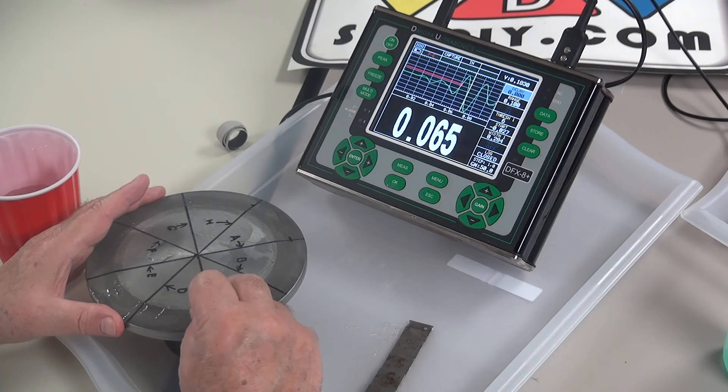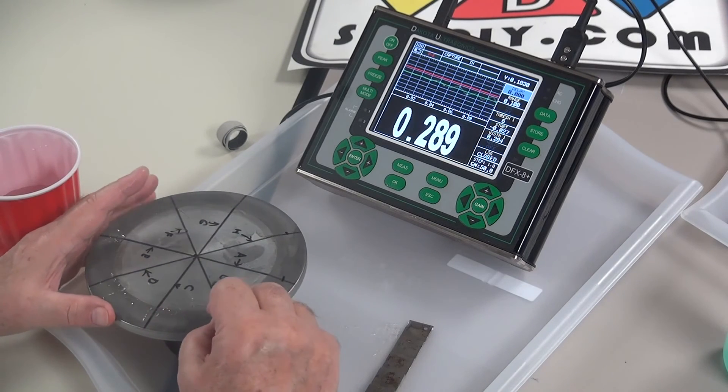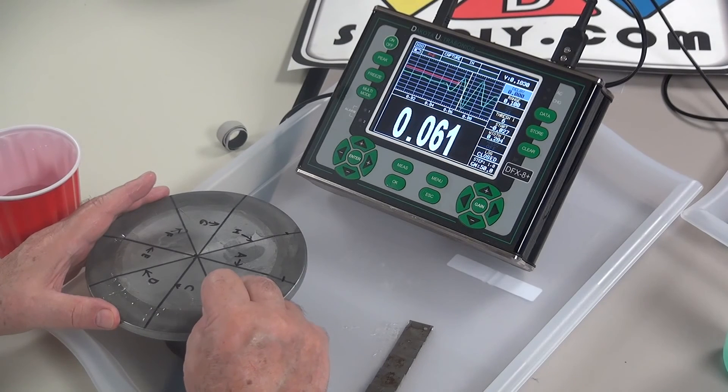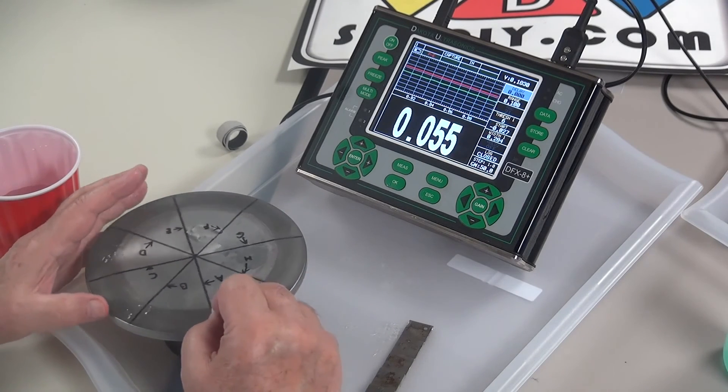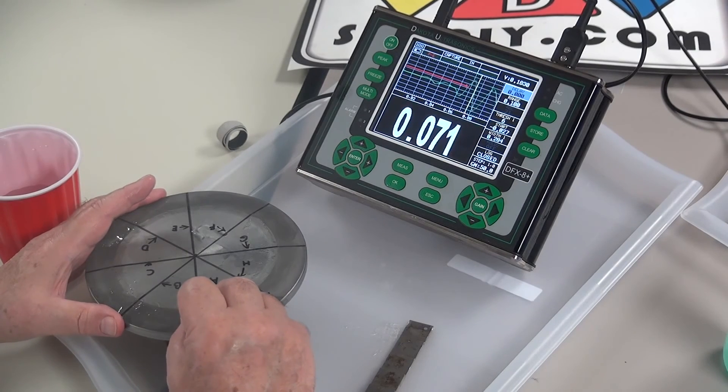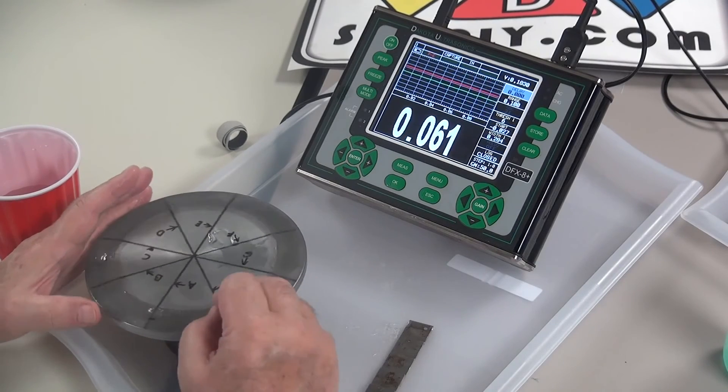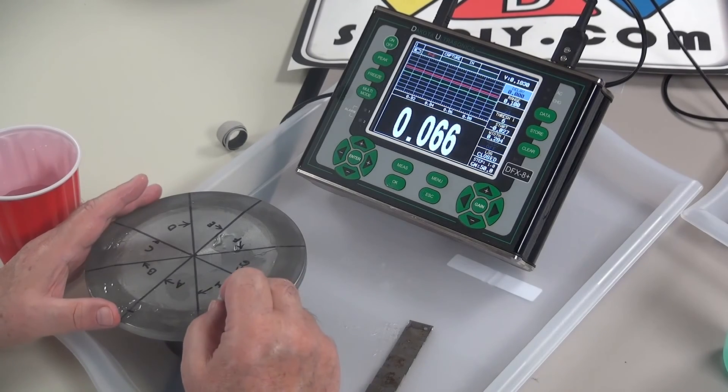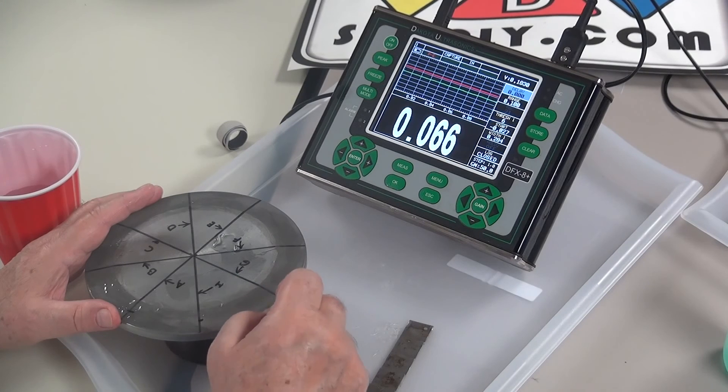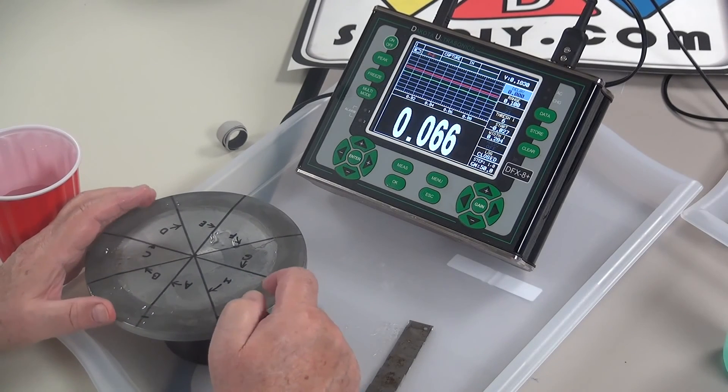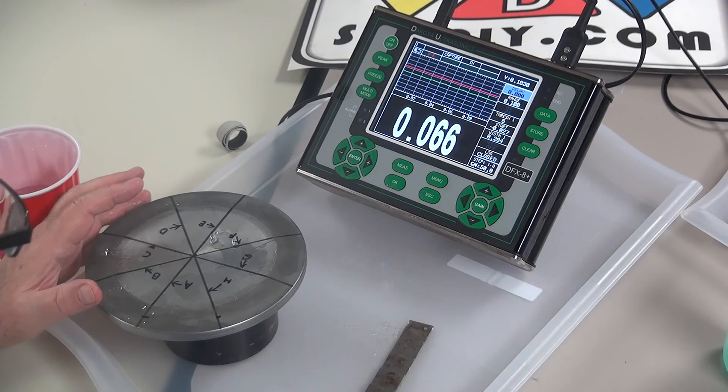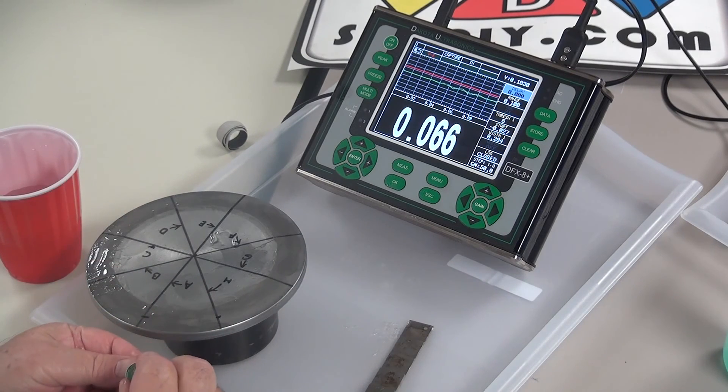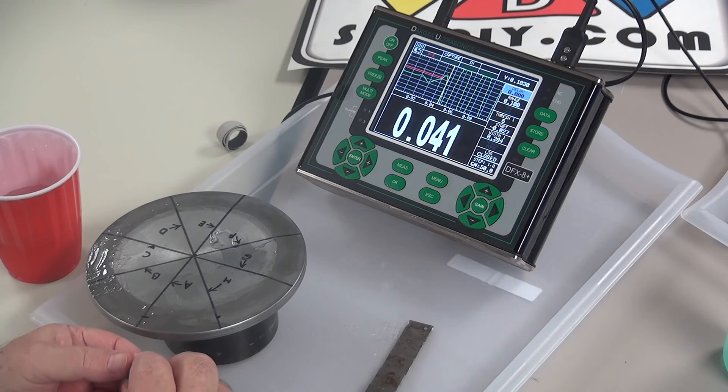And we'll note that our calibration may not be exact because of not having appropriate reference standards. Our calibration is using shims of tungsten of known thickness over air. And obviously we have tungsten to moly. The difference is significant both in signal amplitude and in the phase of the signal.